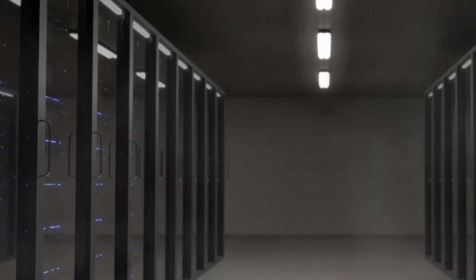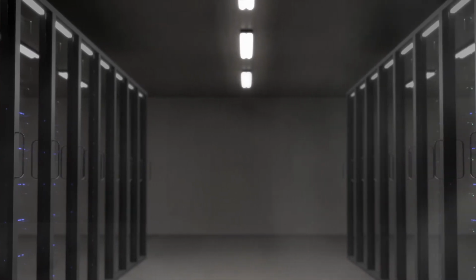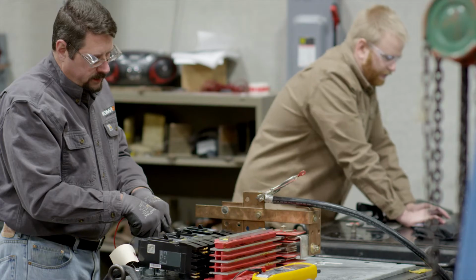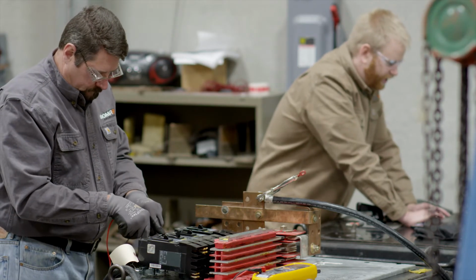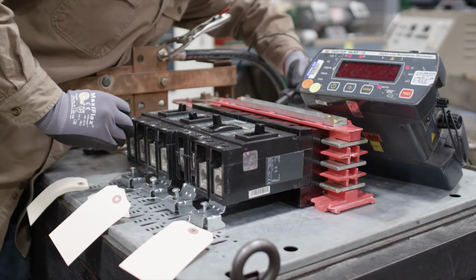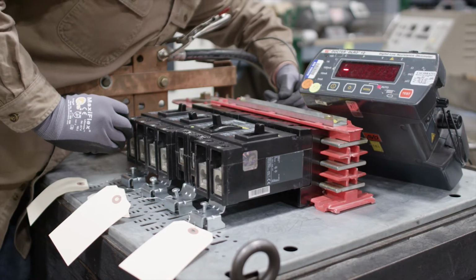There are ways you can minimize the shutdown time. If this portion of the building can't be shut down, bring in a backup generator to keep power to that portion, which allows you to test the rest of it. We have the equipment to test breakers at a very rapid speed, given the equipment and technicians we have to do that testing.